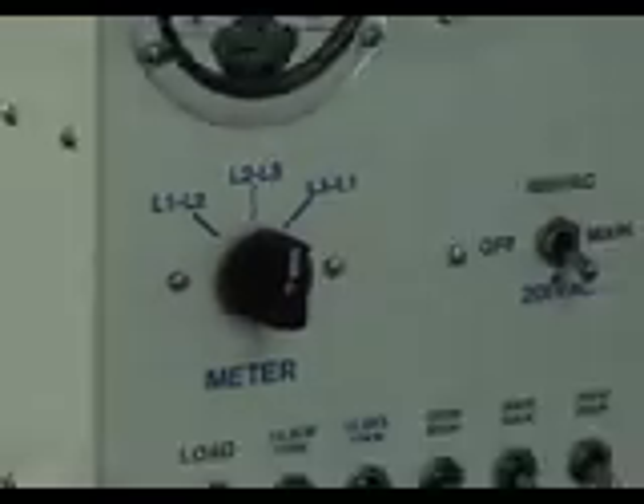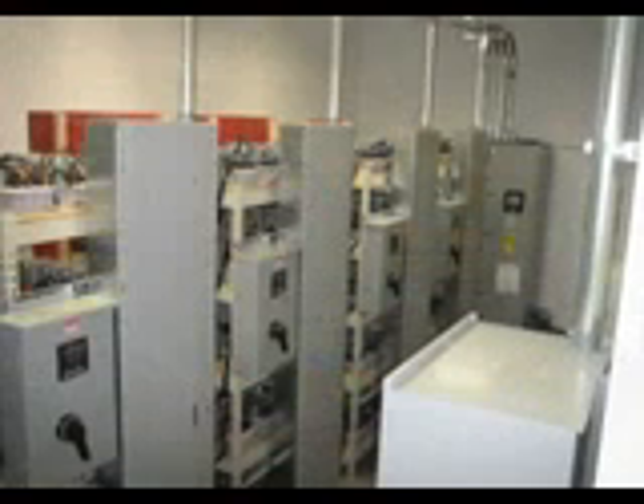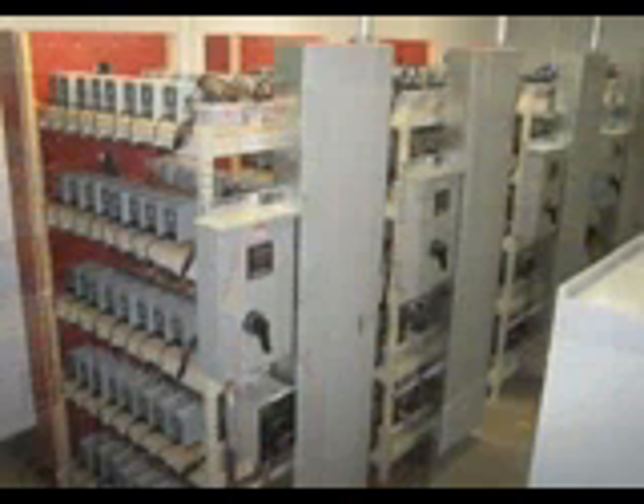It's very easy to see why many manufacturers will only want to test with linear load, as the linear load bank shown here cost around $7,000 to purchase. This represents about 70 kilowatts of load. To create nonlinear load banks for testing, Eaton has custom created computer power supply racks to be the source for nonlinear load. Each rack, which cost around $15,000 to build, consumes about 35 to 40 kVA. The testing facility currently has 4 of these racks to produce a load on transformers around 150 kVA.